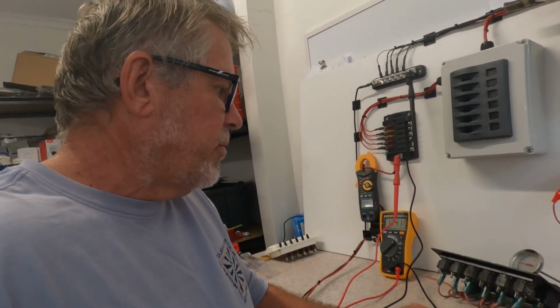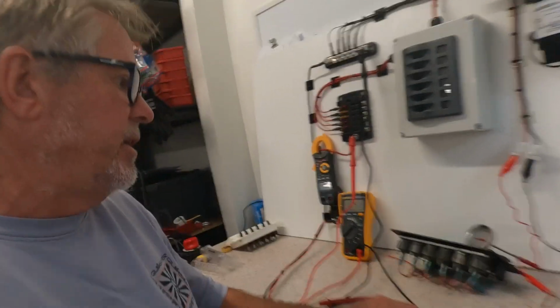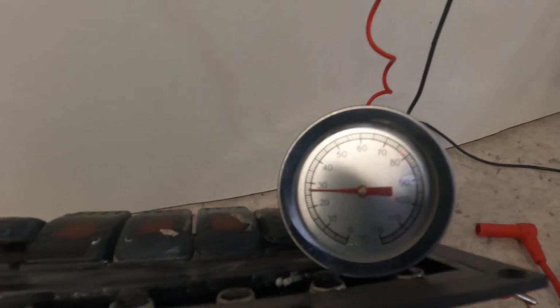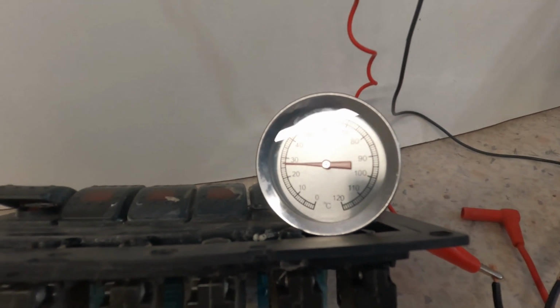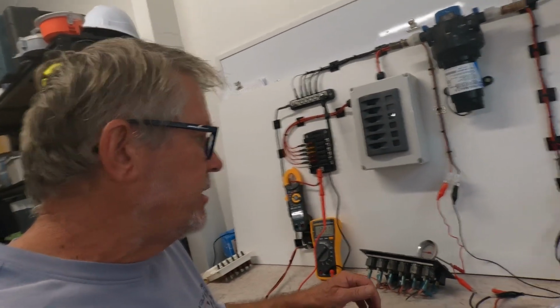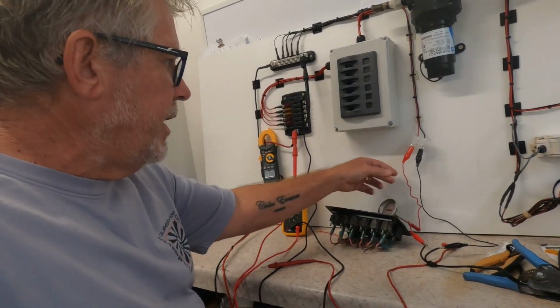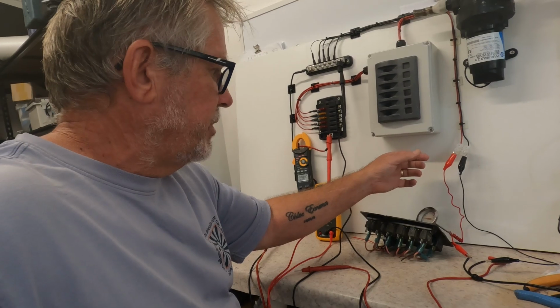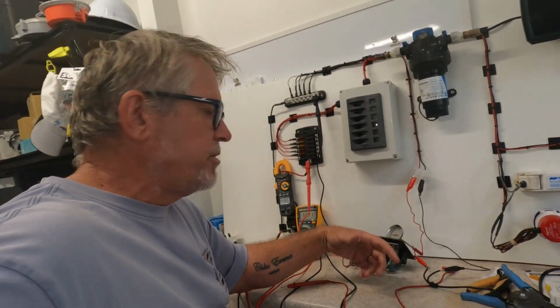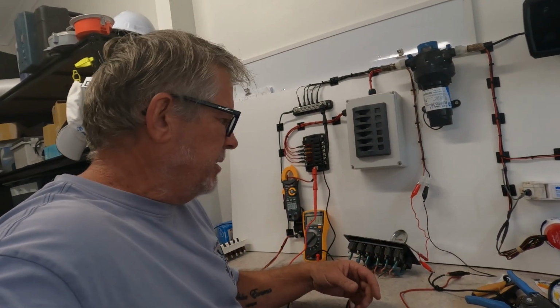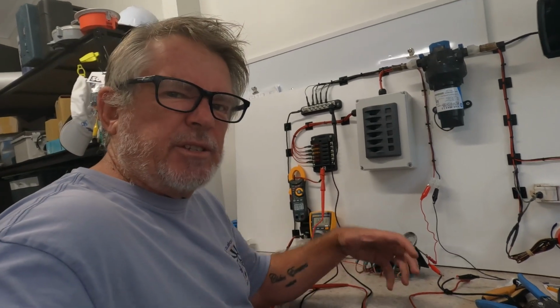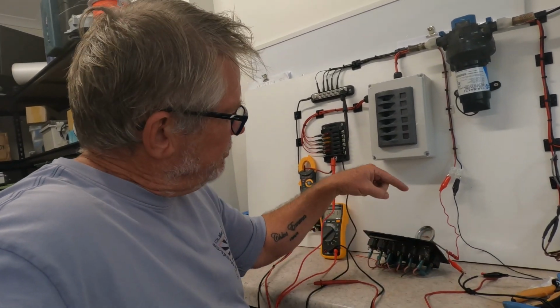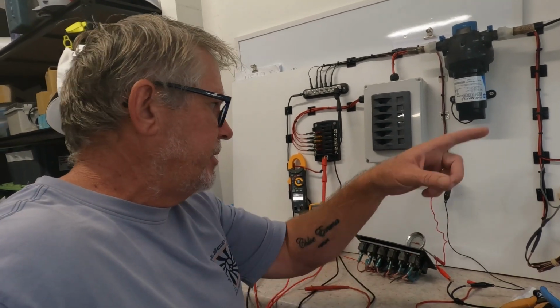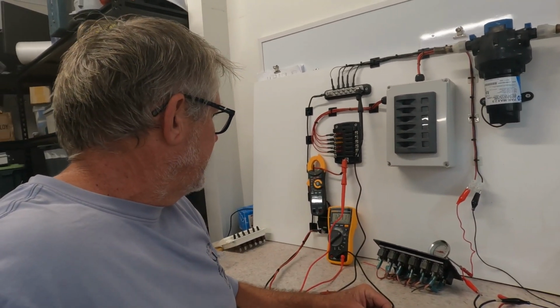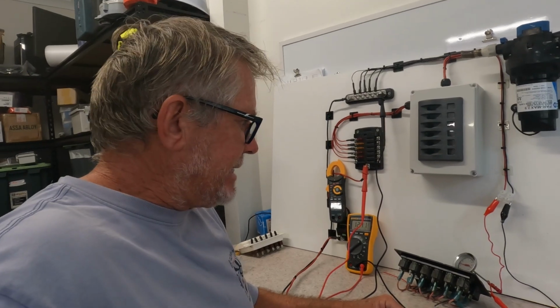So what I want to do here is watch this little thermometer, which will show us whether there's any heat building up in these wires, because we're going to be drawing a fair bit of current through them. It's only about 10 amps, not a huge amount, but it's an example of what happens if you've got a wire that's too small for the load you're supplying. We're going to draw 10 amps through a tiny little wire. Let's have a look at it and see what it does.